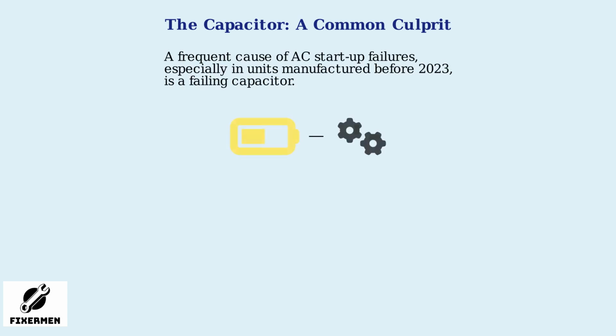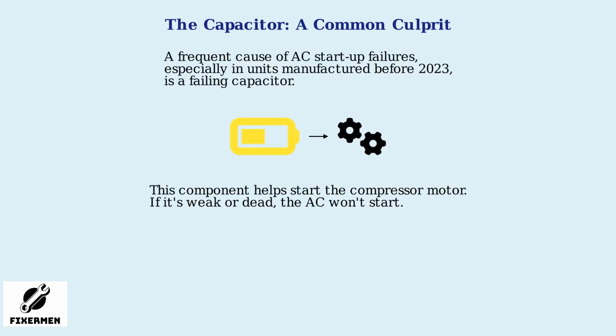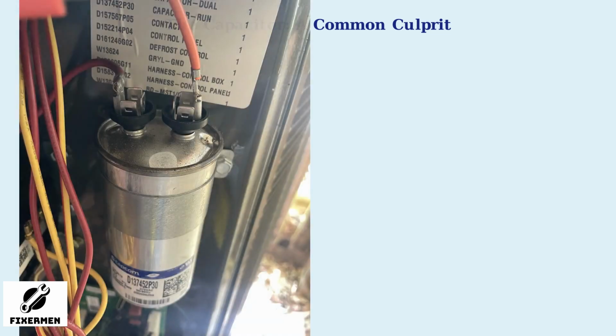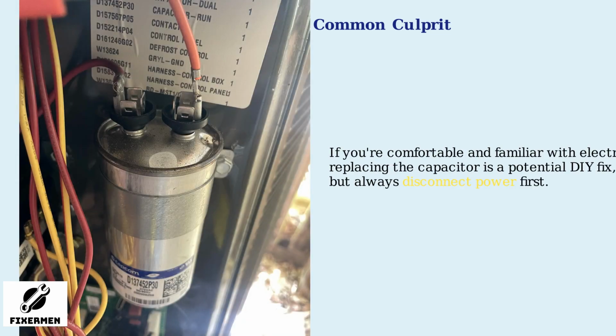A frequent cause of AC startup failures, especially in units manufactured before 2023, is a failing capacitor. This component helps start the compressor motor. If it's weak or dead, the AC won't start. While testing a capacitor requires a multimeter and some electrical knowledge, visual signs like bulging or leaking indicate a problem. If you're comfortable and familiar with electrical work, replacing the capacitor is a potential DIY fix, but always disconnect power first.